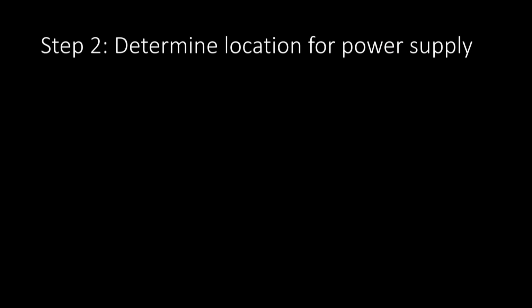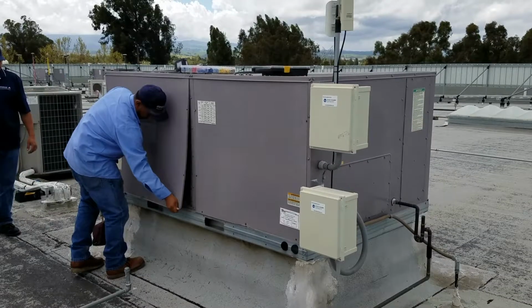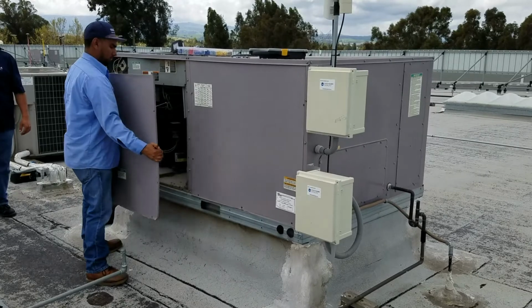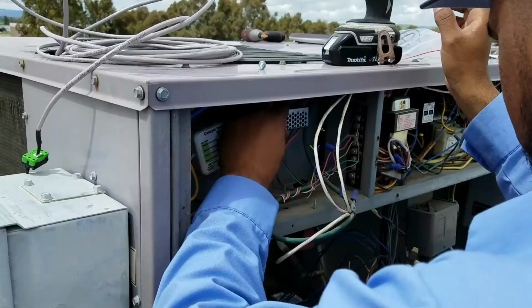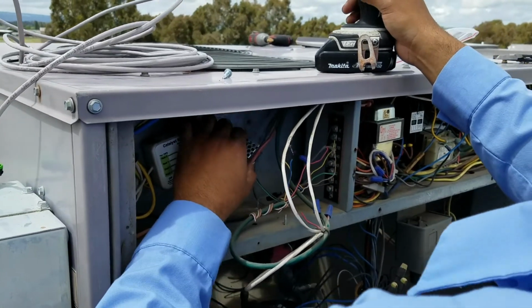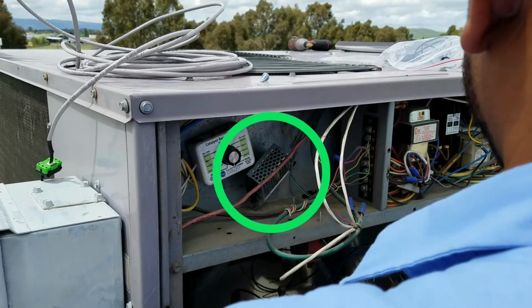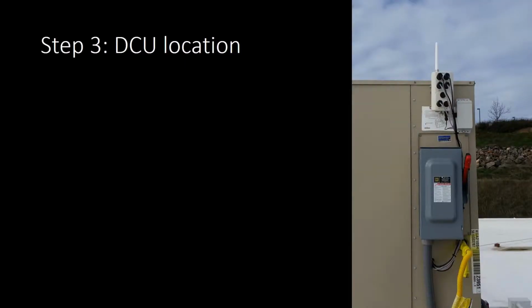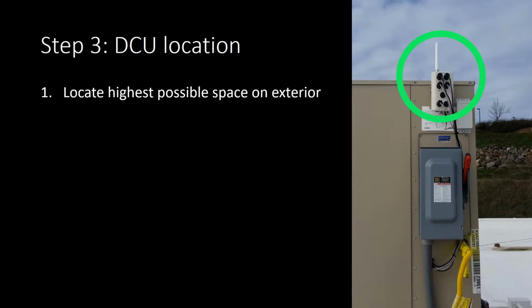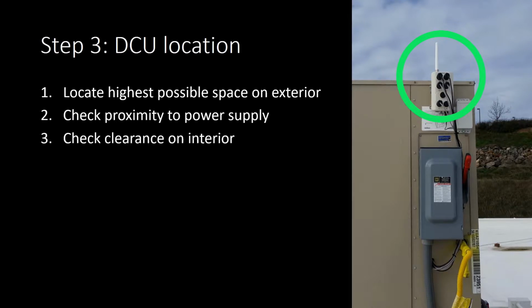Step 2. Determine a suitable location for the power supply. Open the service panel and find an open spot where the power supply can be mounted on the interior of the unit. Make a note of this location. Step 3. Determine a suitable location for the data collection unit. Pick an open spot on the exterior of the HVAC unit which is close to the power supply location. Check for clearance and obstruction on the interior of the unit so the components are not impacted when drilling.